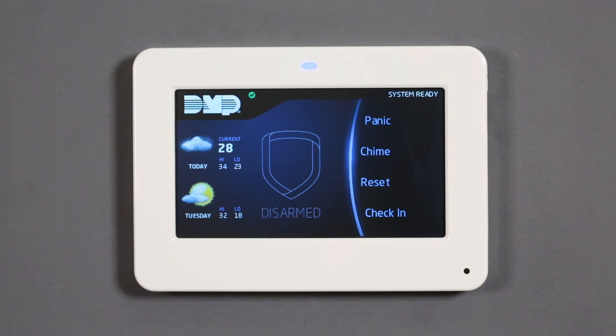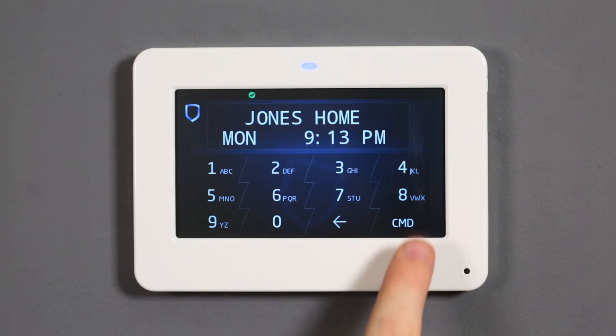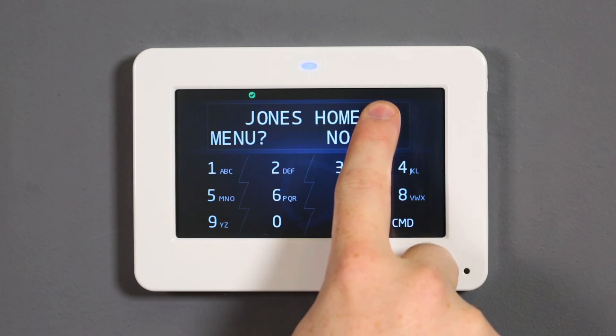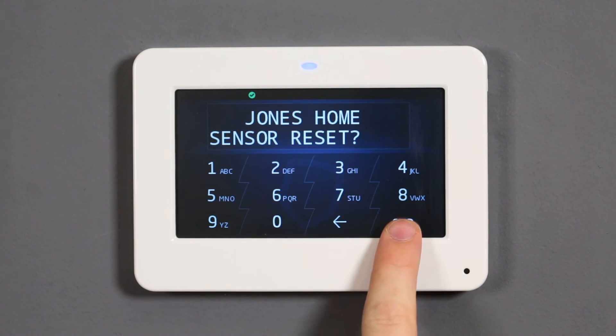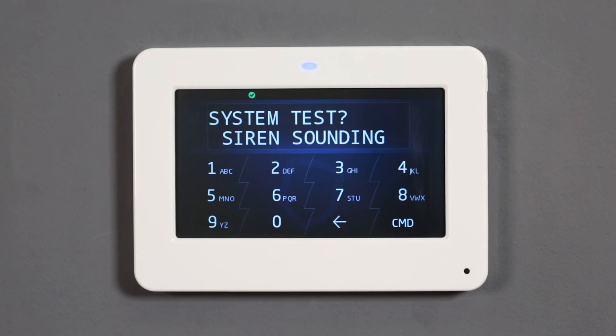Verify that the 763 is communicating to your central station by performing a quick communication test. Navigate to the user menu at the keypad by pressing command until the user menu prompt displays. Select yes and enter your user code. Press command until system test is displayed, then press a top row select area to begin the system test. The panel will test the local annunciators and perform a transmit test to the central station. The keypad will display transmit ok when the test is successful.